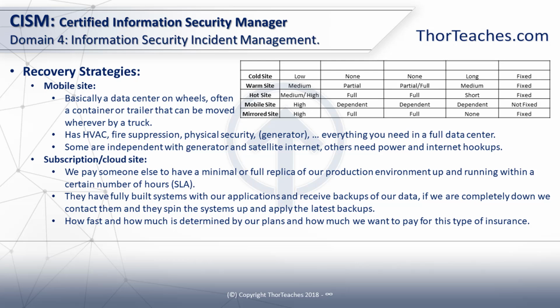The mobile site is basically a data center on wheels, either in a container or a trailer that can be moved by a truck. It is spec'd like a full data center: heating and air conditioning, fire suppression, physical security, UPS. It may at times also have a generator. Some of them are entirely independent, meaning they have their own generator, they have their own satellite internet. Other types, you might need to drive somewhere and hook them up to power and internet. I haven't seen a lot of those around either because they're just not cost effective, but there are places where they would make sense. More and more commonly now is subscription or cloud sites.